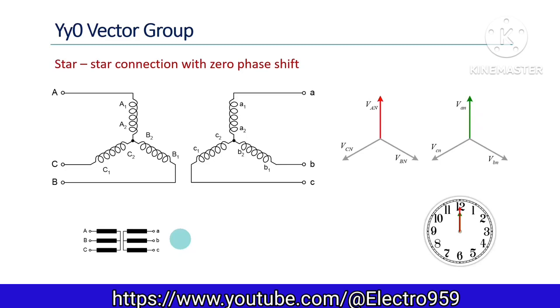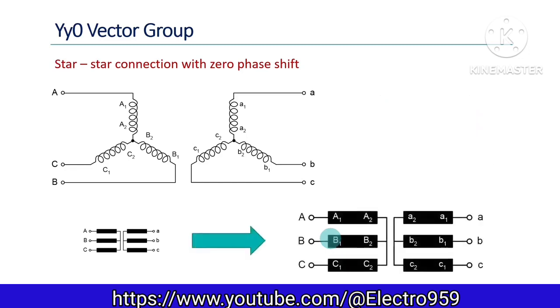We can have a simplified connection diagram, which will normally be printed on the transformer nameplate, and also a displacement diagram which shows the connections of the two windings and indicates the phase difference between them. In the simplified connection diagram, the polarities of each winding are represented as follows: on the primary side, A1, B1, C1 are on the left side, and on the secondary side, A1, B1, and C1 are on the right side. The primary terminals are represented with uppercase letters A, B, and C, and the secondary terminals with lowercase letters a, b, and c. We shall follow this convention throughout this video.